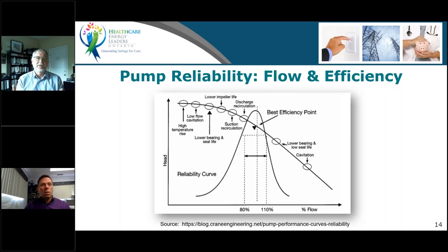So to me, efficiency and reliability go hand in hand. If we treat a pump properly, it's going to operate efficiently. If we treat it improperly, it's the fugitive energy that we're using inefficiently that's doing all this damage. It's the energy that we're not converting to the flow that we really need. Some people call that fugitive energy. So a good way to look for an opportunity to improve the efficiency of a pump system is to go look for your least reliable pumping systems. If you've got ones that are chronically suffering from these problems, those are probably the ones operating at lower efficiency. And so now you get that dual benefit.